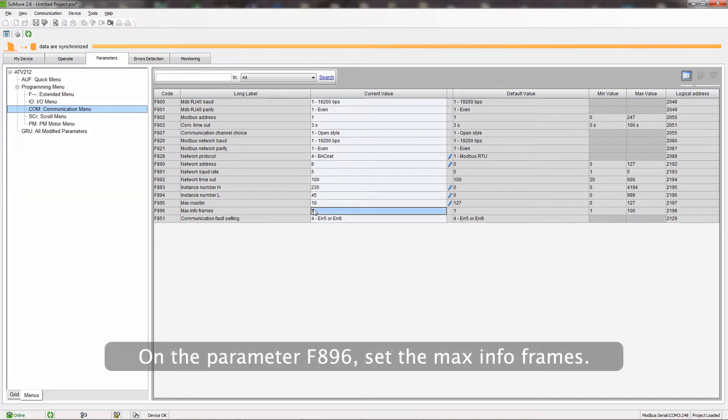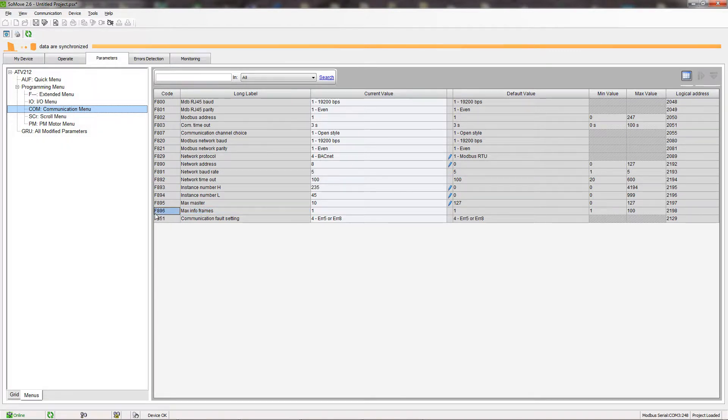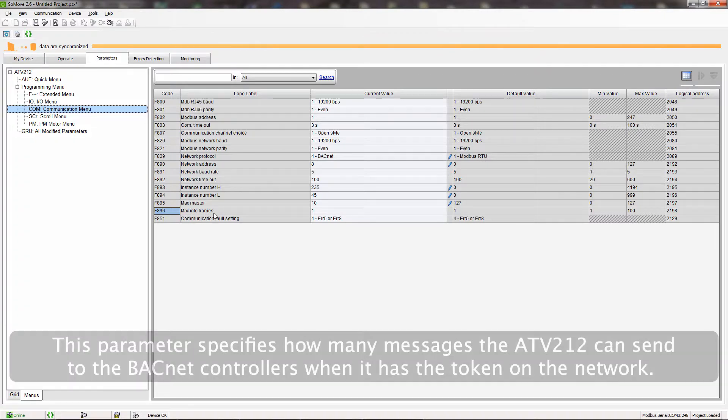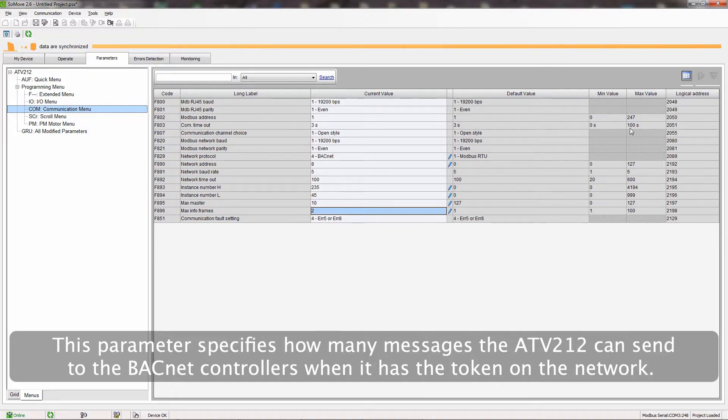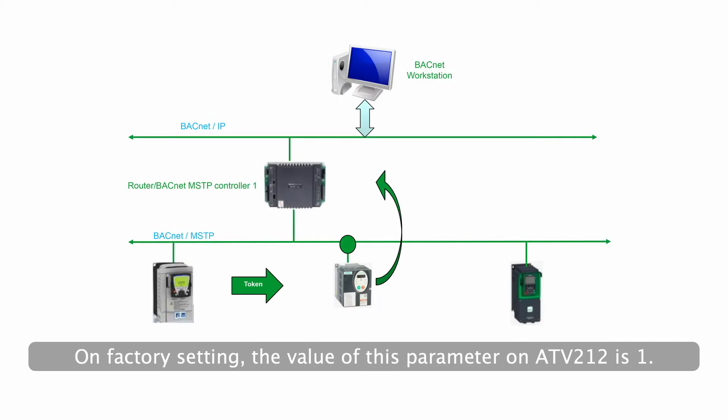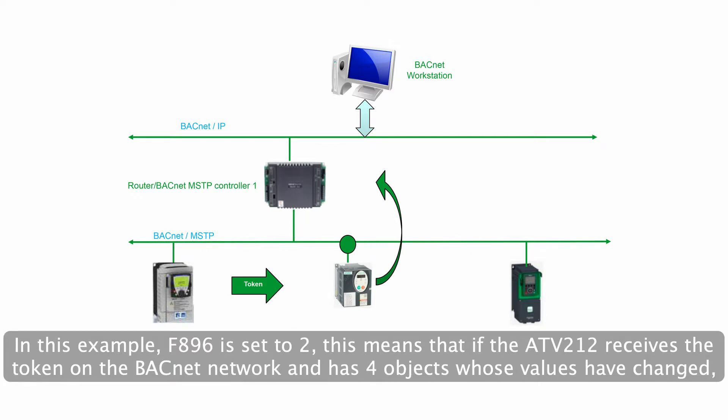On the parameter F896, set the MaxInfoFrames. This parameter specifies how many messages the ATV212 can send to the BACnet controllers when it has the token on the network. On factory setting, the value of this parameter on ATV212 is 1. In this example, F896 is set to 2.